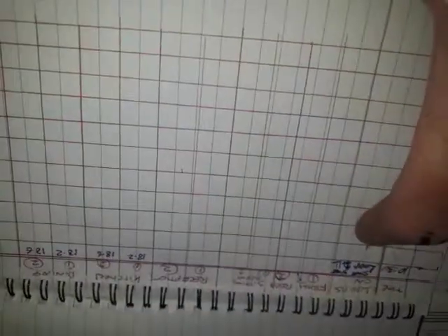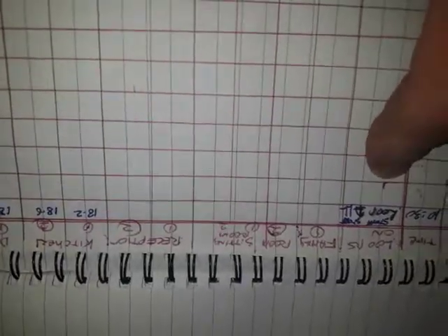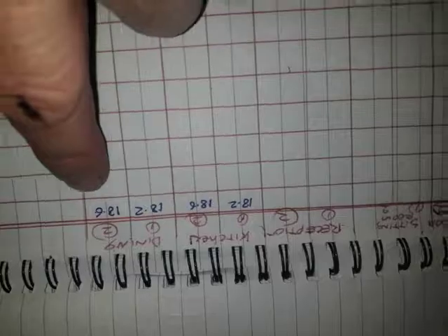So I'm going to start my experiment by having 1 loop on in the house only, waiting several hours, typically 2 to 5 hours depending on the floor covering. Wood takes longer to react, and then I will make my measurements again. And we should see after that length of time that there's a temperature rise in some place in the house.